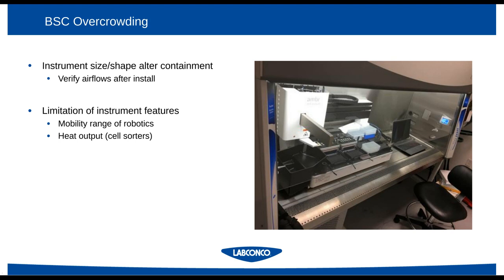The most common type of biosafety cabinet is a type A2, a Class II type A2, and it recirculates a portion of its air, which also means that it will recirculate a portion of its heat output. And for instruments, especially cell sorters and flow cytometers, that can be problematic.